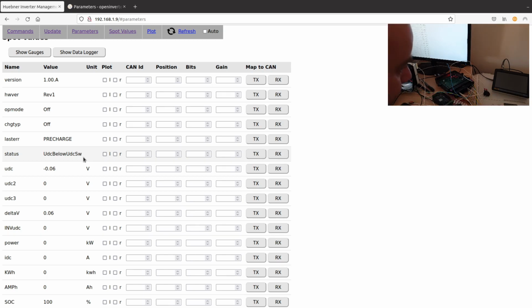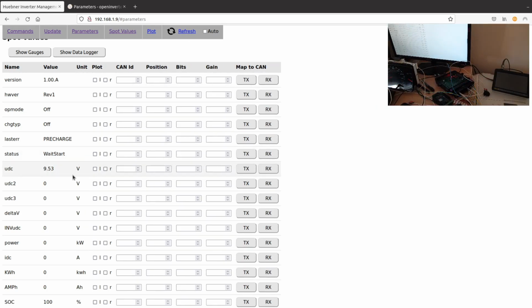If I reconnect my ISA shunt and hit refresh, we see our UDC comes back up. If I press my start button again — that's our key to the start position — and refresh, we're indeed back in run mode with status none. Switching off one more time, we're in off mode.